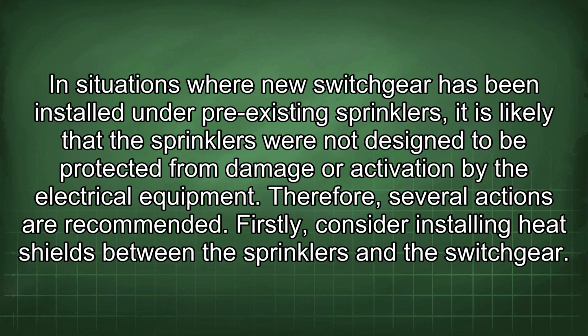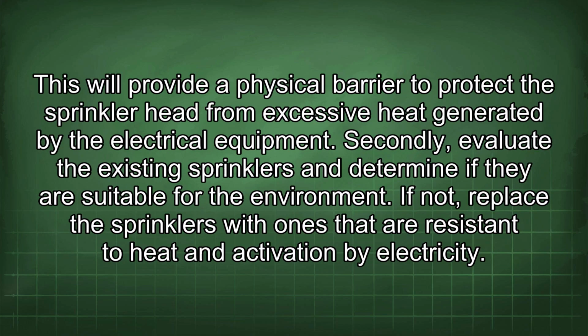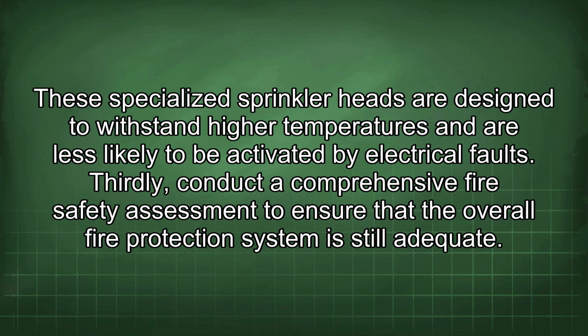Therefore, several actions are recommended. Firstly, consider installing heat shields between the sprinklers and the switchgear. This will provide a physical barrier to protect the sprinkler head from excessive heat generated by the electrical equipment. Secondly, evaluate the existing sprinklers and determine if they are suitable for the environment. If not, replace the sprinklers with ones that are resistant to heat and activation by electricity. These specialized sprinkler heads are designed to withstand higher temperatures and are less likely to be activated by electrical faults.